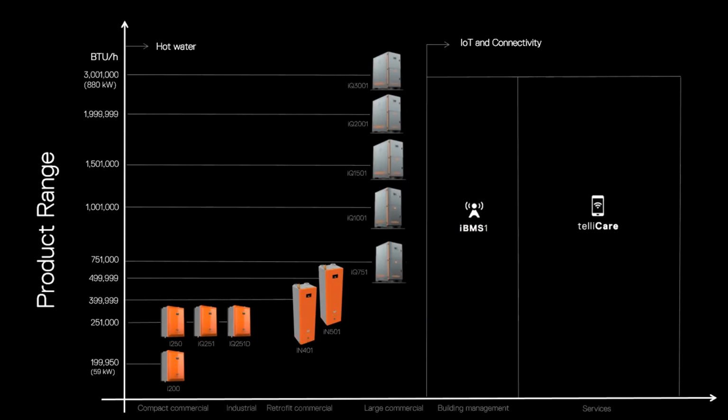Those are all single heat exchanger units. Then we go up to the 401 and 501, which are multiple heat exchanger units. Those have 2 in there, so that's 400 and 500,000 BTUs. Those are a drop-in solution for a tank type heater. If you're replacing a tank type heater and you have the exact same floor, you pull that out and put one of these in. It's got the same basic connection sizes and locations, so there's very minimal piping.